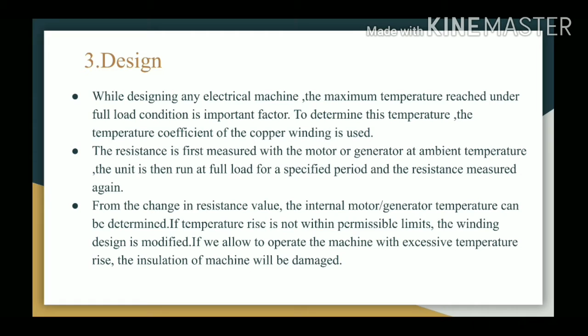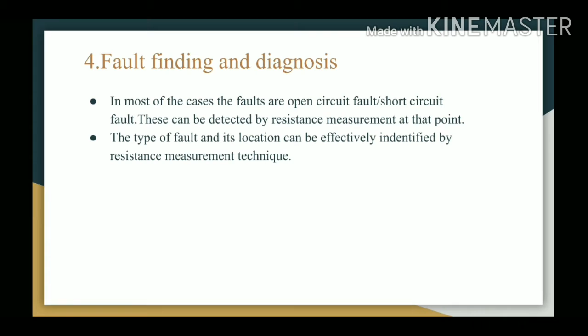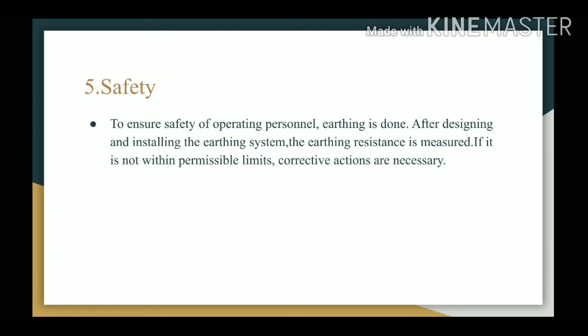Fourth is fault finding and diagnosis. In most of the cases, the faults are open circuit fault or short circuit fault. This can be detected by resistance measurement at that point. The type of fault and its location can be effectively identified by resistance measurement technique. Fifth is safety. To ensure safety of operating personnel, earthing is done. After designing and installing the earthing system, the earthing resistance is measured. If it is not within permissible limits, corrective actions are necessary.